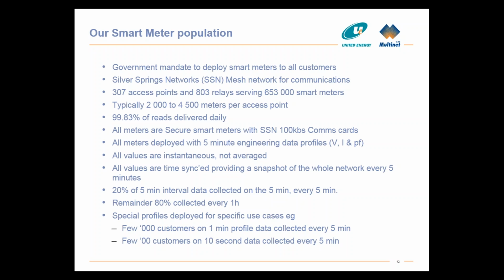If we briefly look at our smart meter population, we had the mandate to deploy smart meters to all our customers, so each and every customer that could get a smart meter got one — in total 653,000 of them. We use the Silver Springs mesh radio communication to all of them and read them every day, with a daily success rate of 99.83%. At this stage, the billing data is retrieved every hour. The generation we've got, since we started the installation some time ago, actually uses the slower communication network, so we're unfortunately limited to 100 kilobits per second communications.